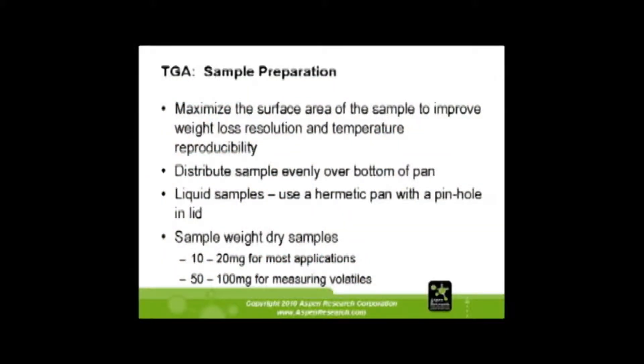You want to maximize your surface area — it will improve your weight loss resolution and your temperature reproducibility. You want to distribute the material evenly over the bottom of the pan. Liquids can be run in hermetically sealed pans with a hole in them. When you run a liquid on a TGA pan it tends to boil over the edge, so it's nice to hold it inside a sealed pan. Sample sizes of 10 to 20 mg for most dry applications and 50 to 100 mg for other measurements.